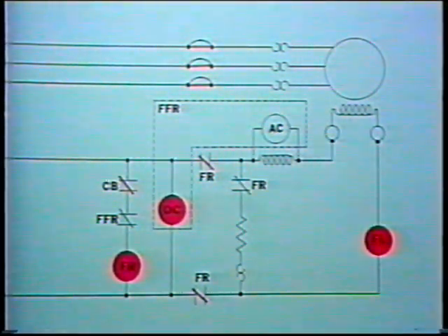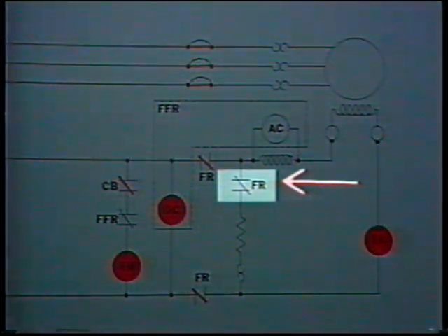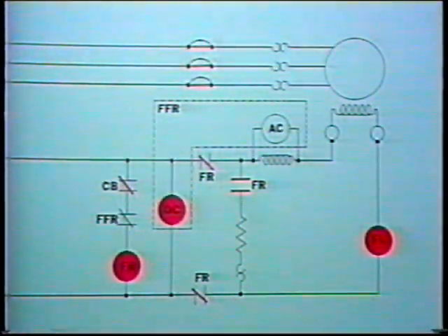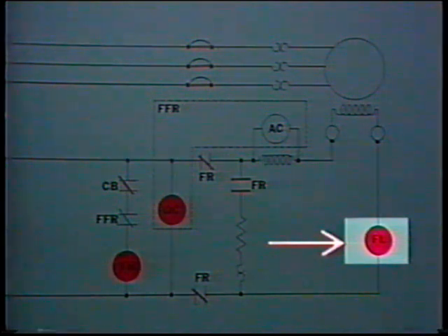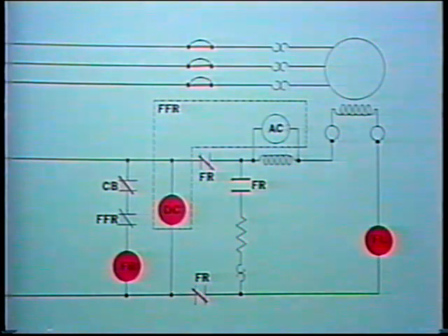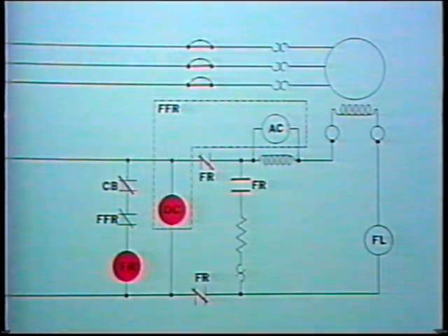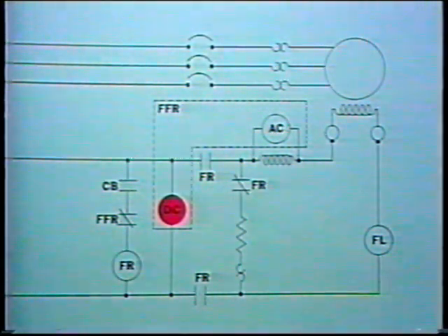At the same time, the field relay opens contacts in this part of the circuit. That eliminates the components that are only needed when there is induced current flow through the rotor. There's still another relay in this synchronous motor controller, and that's a field loss relay. A field loss relay trips the stator circuit breaker if excitation current is lost during motor operation. When the field relay contacts are closed, direct current flows through the field loss coil. If direct current is lost, the coil is de-energized and trips the circuit breaker to stop the motor. That prevents continued operation by induction, which could damage the motor.